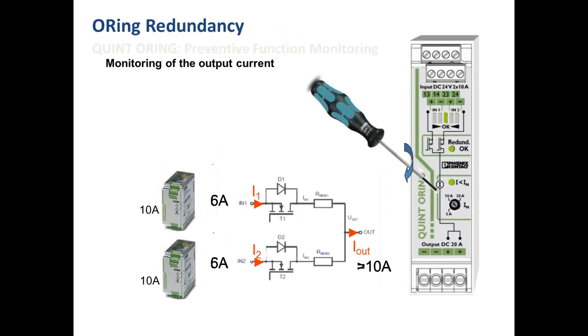Okay, let's switch gears and talk about redundancy. When it comes to redundancy, there's an exciting new technology based on a MOSFET design. This device is called an ORing redundancy module. The benefit of using a MOSFET-based redundancy module over a power diode-based unit is the much lower heat dissipation. An advanced feature of the ORing redundancy module is also exciting. It's the ability to monitor the load current. This ability takes the place of an additional device in the power system. In a 10 amp redundant system, the ORing module will alarm if the load draws more than 10 amps.